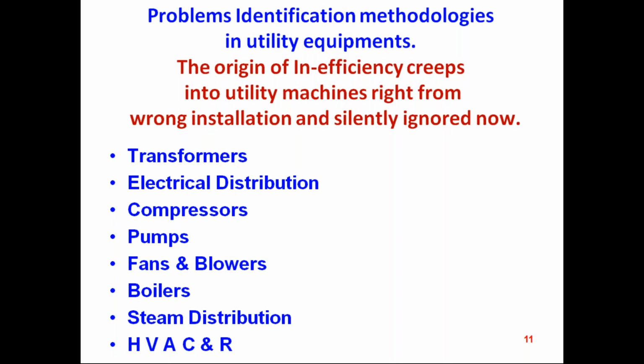So for the application of a VFD, the energy auditor has to give a careful suggestion. Where do they need a VFD? Where do they not need a VFD? And what is the purpose of the VFD for the given system? The loading decides the VFD retrofit for the given system. The same case applies to the pumps, especially the centrifugal pumps. This we will go into in depth.